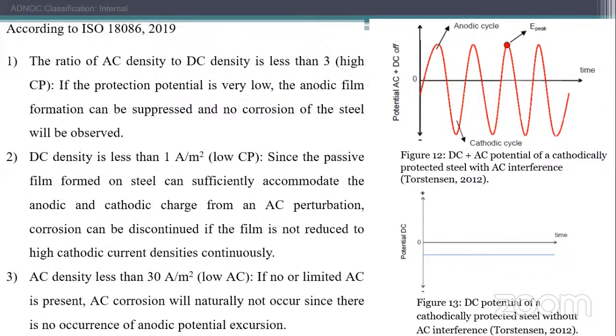So as I said, for corrosion to happen, all of these conditions must be present. If you're able to eliminate any of them, it will not happen. So it's like trying to prevent alternating current corrosion: if I'm able to prevent the negative wave, that metal will never dissolve, rust will never form. According to ISO, if the negative wave, which is the DC density, is less than 1, the passive film cannot dissolve. If the AC density over the positive and over the negative is also less than 3, the process will also not proceed; it will become insignificant on its own.